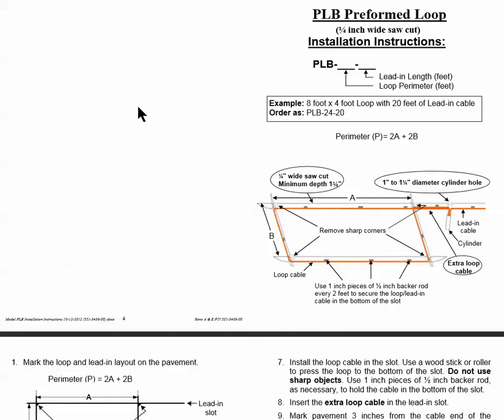The next thing you need to know about loops is that they're very delicate, or at least treat them delicately. The loops are copper wire with insulation around the wire, and a preformed loop is all made up for you. You don't have to hand make it and it's just ready to go into the saw cuts. But any sharp edges, any sharp corners, any sharp gravel left over in the saw cut, anything that can notch into that insulation will wreck the loop. You have to treat that loop wire or the preformed loop with great care, making sure not to damage the insulation.